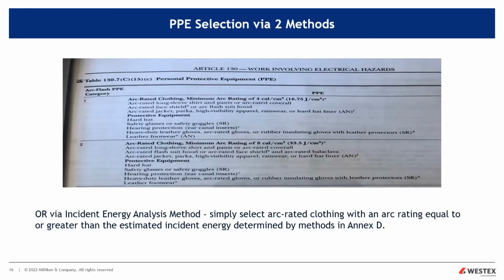So basically, with the changes, is the PPE category still valid? If it is, then you can use the tables. If it's outside the parameters for available fault current maximums or clearing time, then you have to go to an incident energy method. Then, of course, the incident energy method is easy. You just select clothing that has an arc rating higher than the estimated incident energy at that work distance.